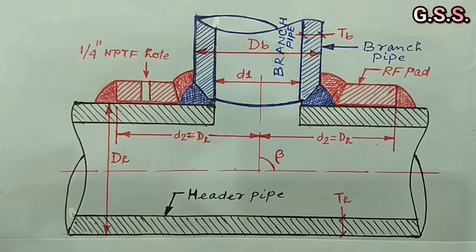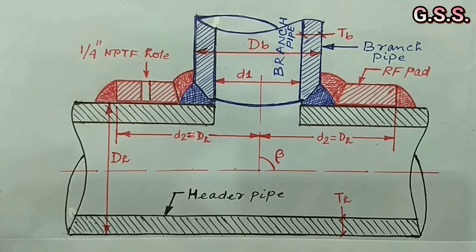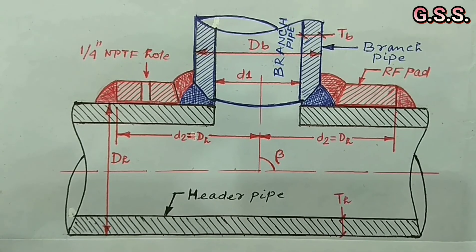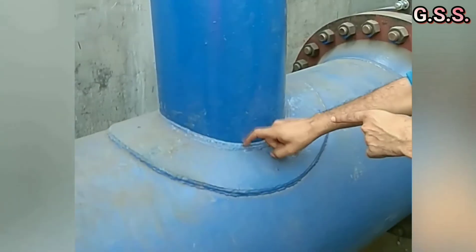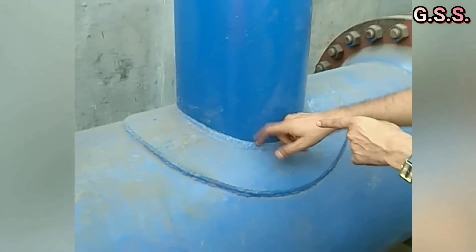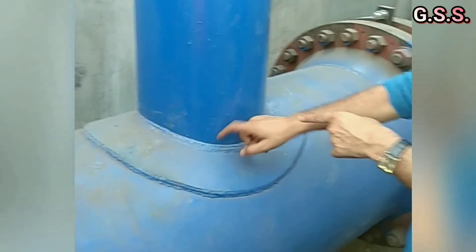Where cyclic operation is there, that means temperature changes in a cyclic manner, direct branching should be avoided. This is an 8 inch by 3 inch unreinforced branching without RF pad and this is a reinforced branching with RF pad.